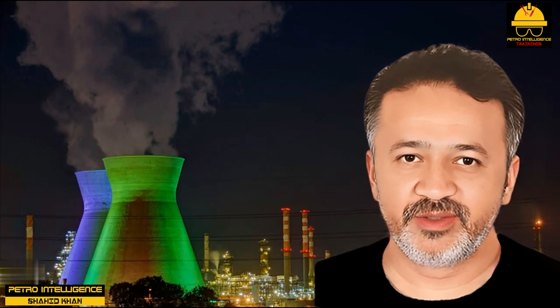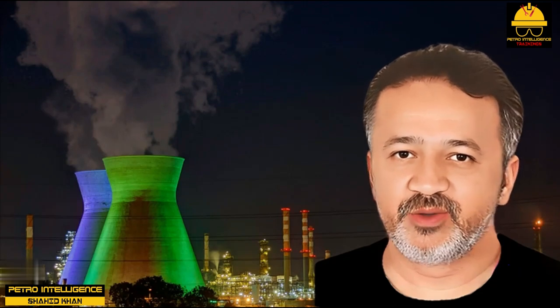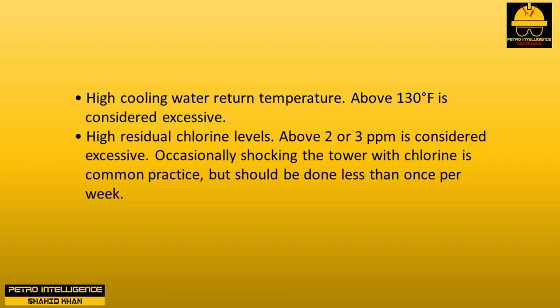Wooden cooling towers: most older cooling towers in the world are constructed of wood. The interior of the tower is filled with wooden slats. The lignin in these wooden slates is removed by the circulating water, causing the slats to break. The failure of the slats degrades air-water contacting, which raises the supply water temperature to the process units. Two things that accelerate the rate of lignin loss are: high cooling water return temperature — above 130°F is considered excessive — and high residual chlorine levels.